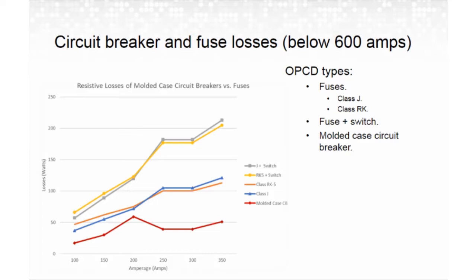The red line at the bottom is a typical molded case circuit breaker. And the increase that we see around 200 amps, I believe, is due to the differences in frame sizes and thus differences in contact area and associated resistance.